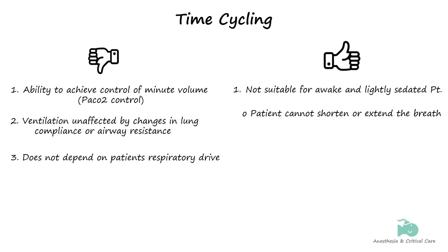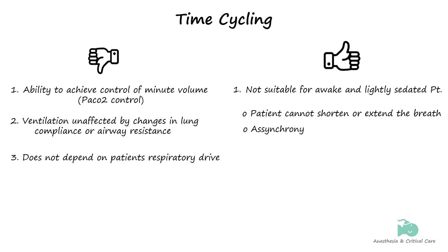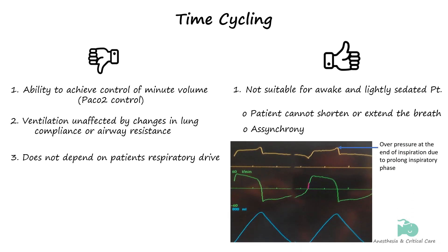Furthermore, there may be patient-ventilator desynchrony, particularly if the patient attempts to exhale before the cycle timer completes its run. This situation can lead to a pressure increase at the end of inspiration, either due to lung compliance reaching a point of overdistension, or because a spontaneously breathing patient decides to exhale before the breath cycle ends.